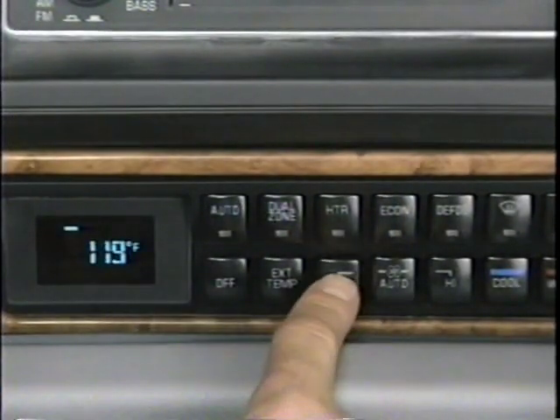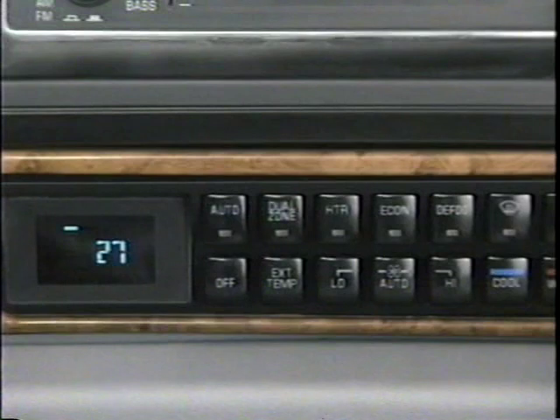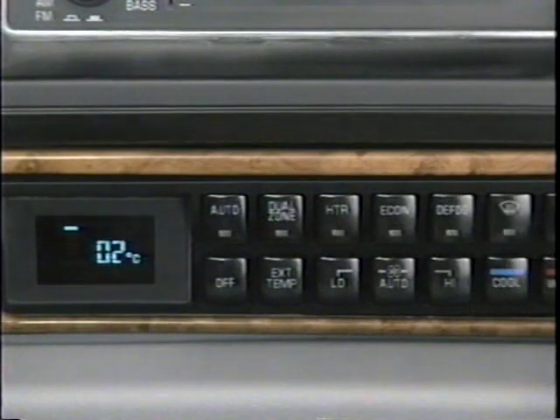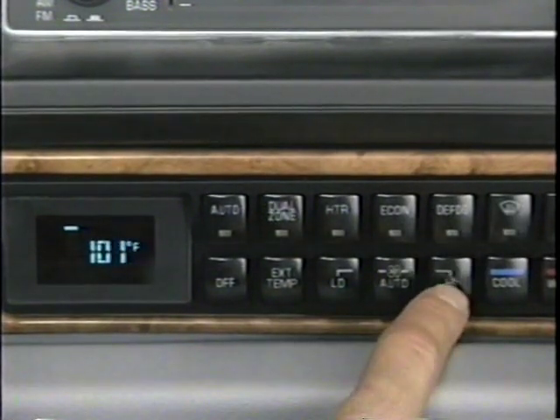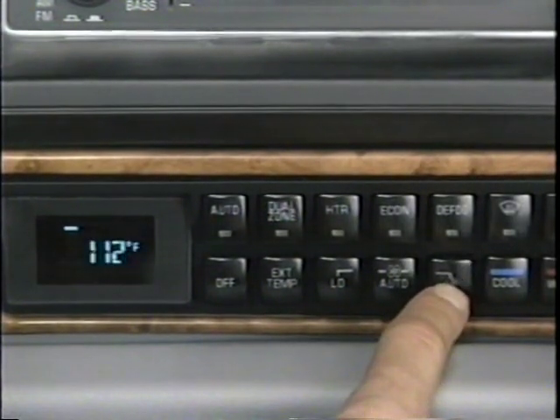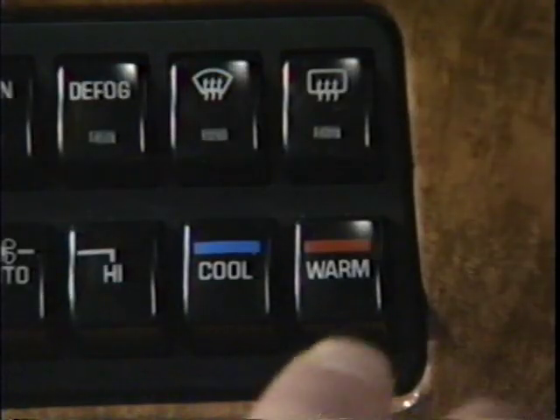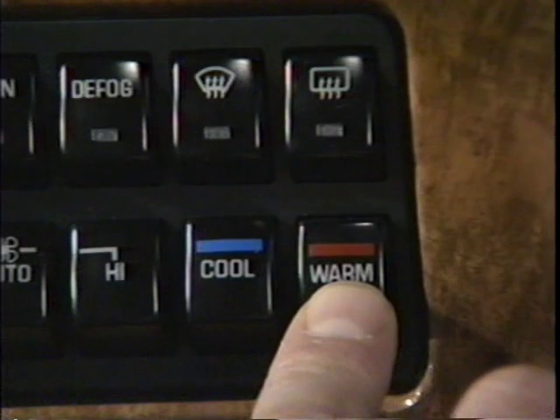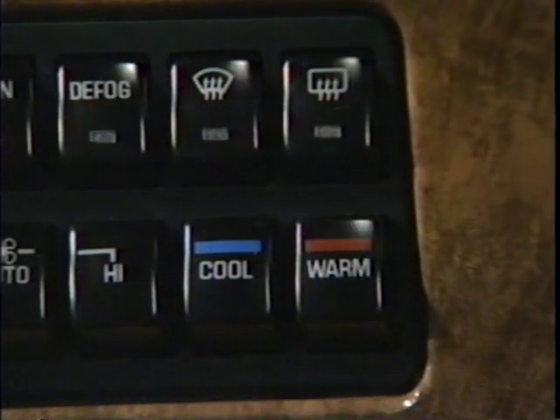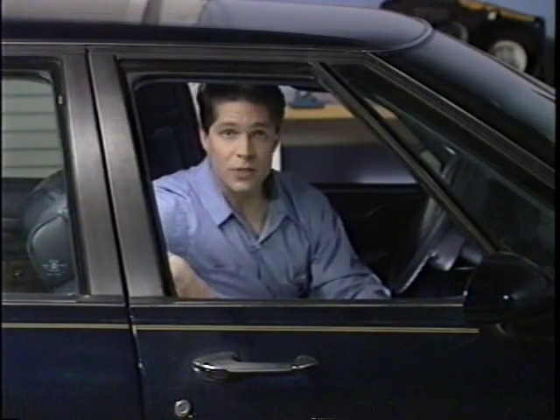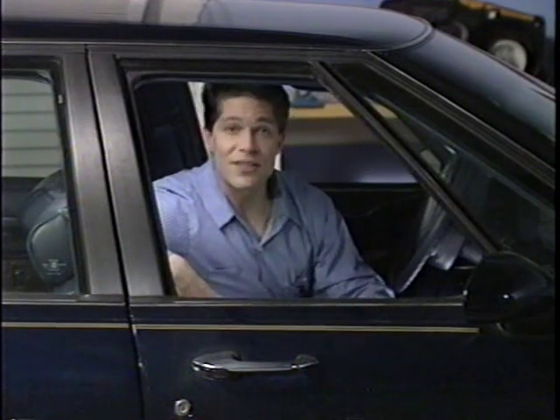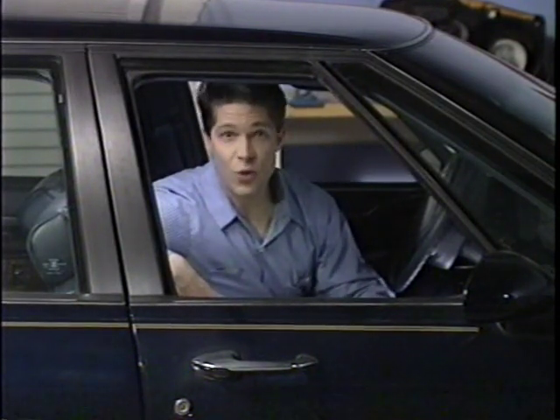To enter the override feature, press low after the segment check until 2 degrees Celsius is displayed. Now, press either the high or low button to cycle through the override list. Once the desired override has been reached, press either the warm or cool buttons to change the value of the selected override. It is also possible to perform these operations using a Tech 1 equipped with the mass storage cartridge.